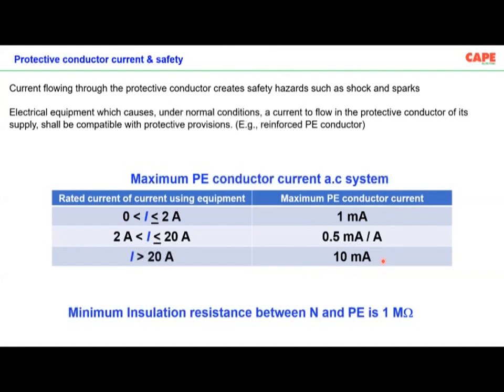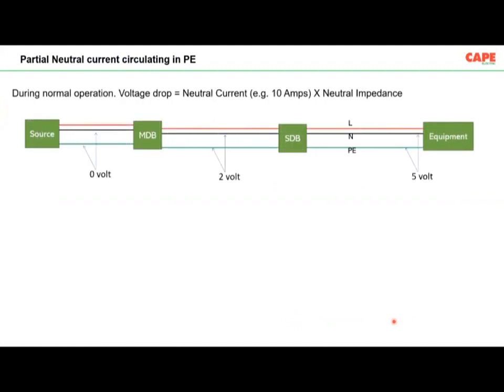How to make the insulation resistance test? You must disconnect your equipment. You must test the insulation resistance of your wiring, including your panel board. You must disconnect your earthing and you must test the insulation resistance between neutral and the protective earthing conductors. The minimum resistance required is 1 megohm. If the resistance is lesser than 1 megohm, then your electrical installation is not in a good condition. This being the fact, practically what do we do? I'm just showing you a classic example.